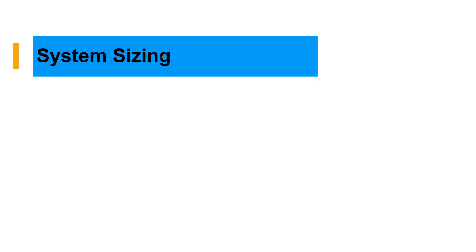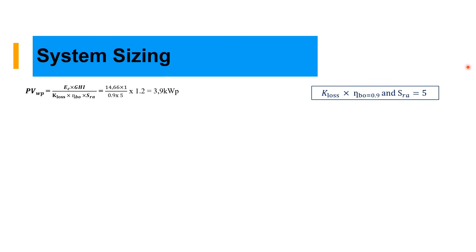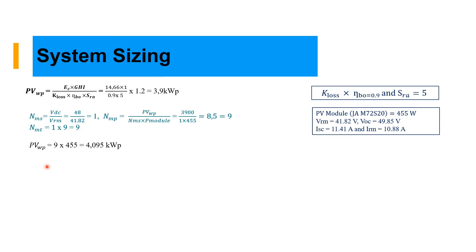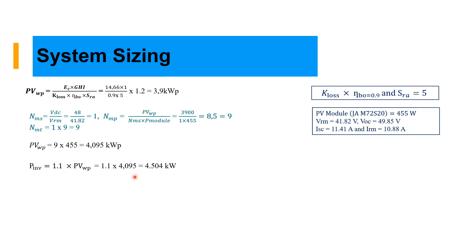Let's continue with our system sizing. Now we are going to substitute the numbers. We have our energy consumption 14.6, the solar irradiance is 1 kilowatt per square meter, losses assuming 0.9 and our solar radiation 5. We can calculate our number of series using DC voltage of 48 and the VRM which is the voltage in our module. According to our calculations, the number of panels in parallel is 9. That means our PV watt peak, our PV size is equal to 4.095 kilowatt peak.